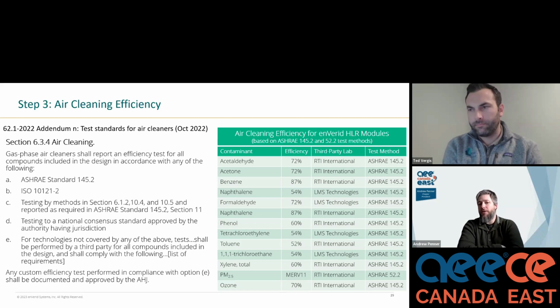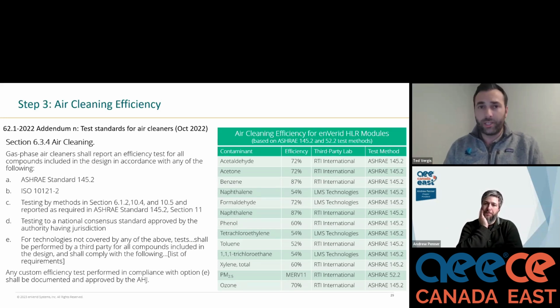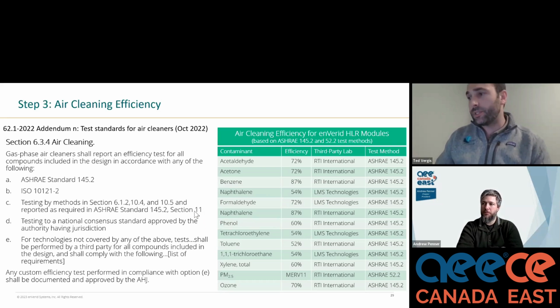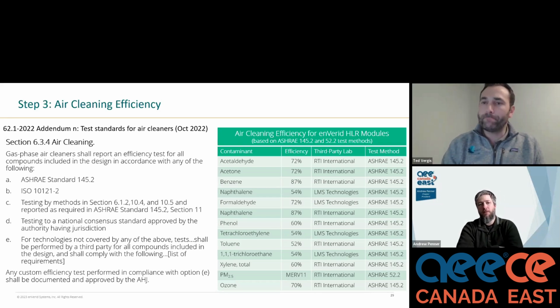The filtration media that you have, it's effective to also remove those contaminants, we're presuming? Yeah, so two benefits there. One is those outdoor generated contaminants: if you need to ventilate that building to the ventilation rate procedure level, you're bringing in more of those contaminants. Not great. So the IAQP actually has a multiplying effect that helps us ensure better indoor air quality, which is one, we're introducing less of those contaminants into the space. And two is these filters do remove those types of contaminants. So NOx, SOx, BTX, those are all derivatives of this list here. BTX is benzene, toluene, and xylene. NOx is similar to that list as well. So yes, we absolutely remove those contaminants of concern, and by introducing less of those into the space, you end up with better IAQ. So yep, absolutely. Yeah, right on.